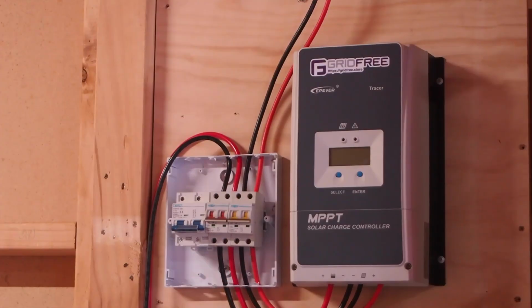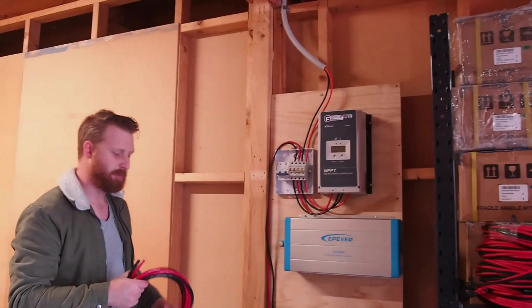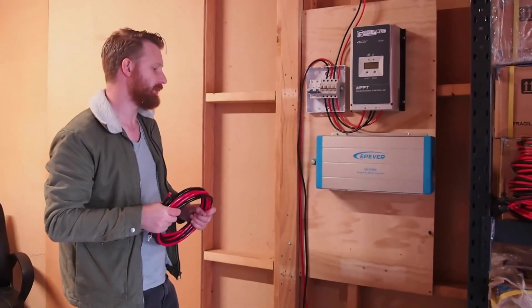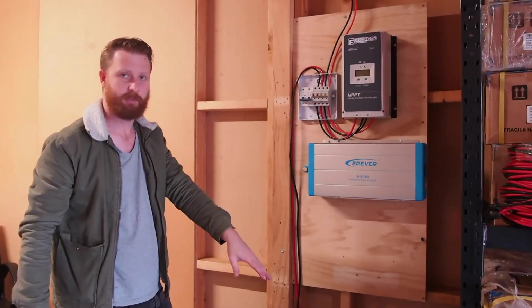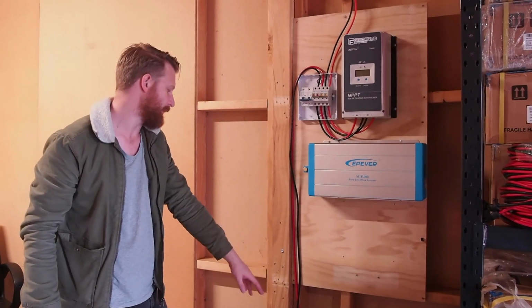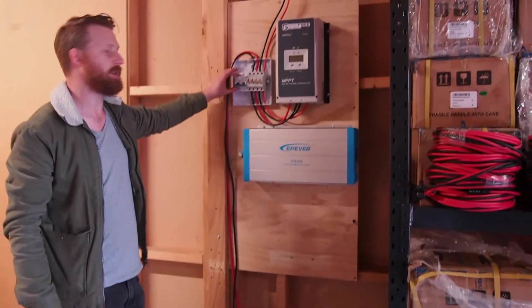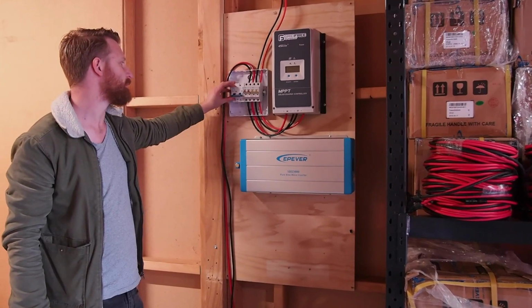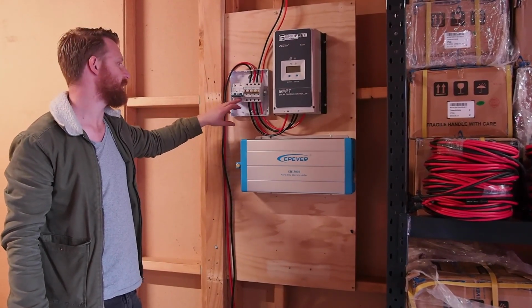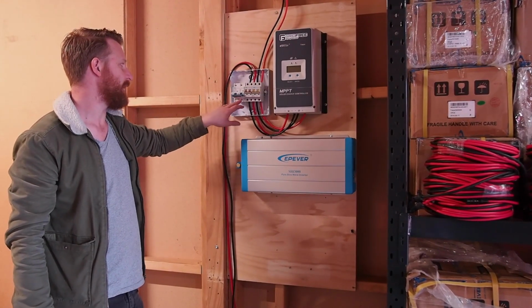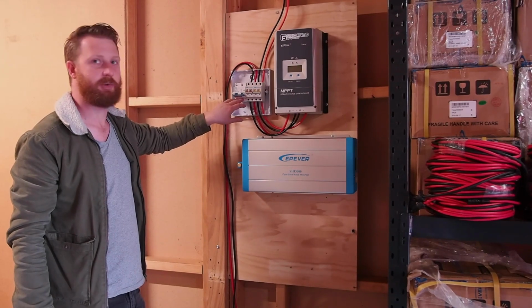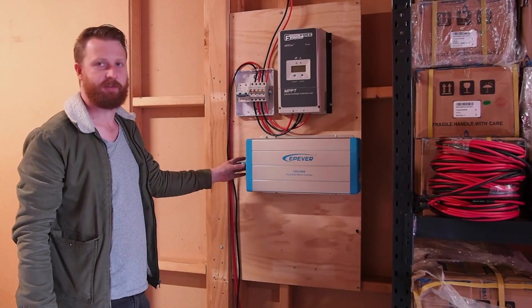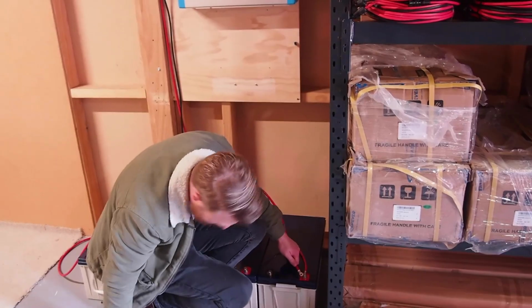So the last cable run we have to do is with the 25mm cable. And we're going to do the same thing again, where we clamp the positive down on this side, we follow the same cable up, or we run it into the 125 amp circuit breaker, and then we make sure to leave the extra that we need to run from the other side of the 125 amp breaker, down to the positive and negative of our inverter.